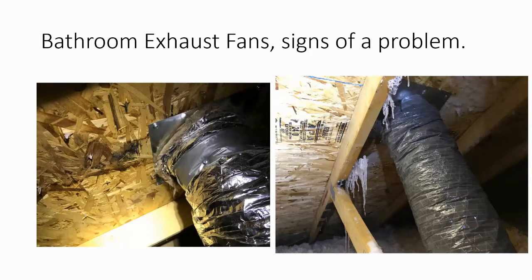Is there any chance with that photo that the roof hood was plugged or stuck shut? Don't really see that with any regularity. Oh, okay. So I was wondering where the back pressure would come from. I should mention there's no connection between the typical gooseneck that's on the roof and the pipe. That's part of the problem. There's no link between the two pieces. In older homes, it's actually just a pipe and a hole in the roof. They did that for a long time. And funny enough, those tend to not give people that much trouble, but this setup does.